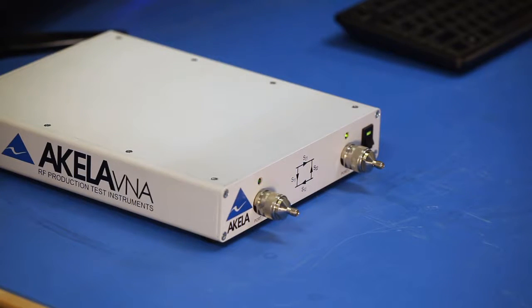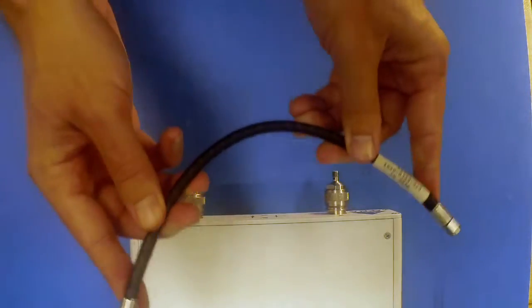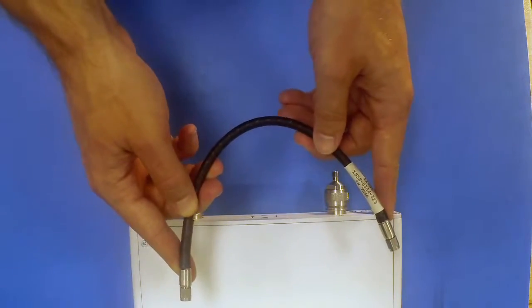So today I'm going to show you how to do a basic two-port calibration of a VNA. To keep things simple, I'm going to use the short, open, load, and through standards because those are pretty cheap and easy to come by from stores all around. What I'm using for my through is a piece of semi-rigid, high-velocity cable.